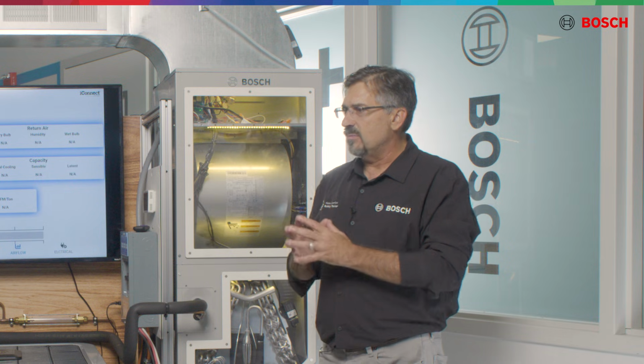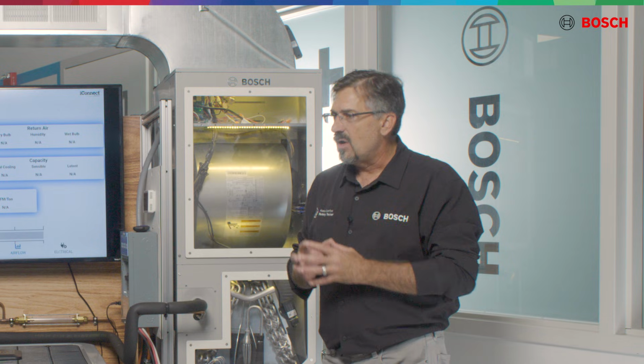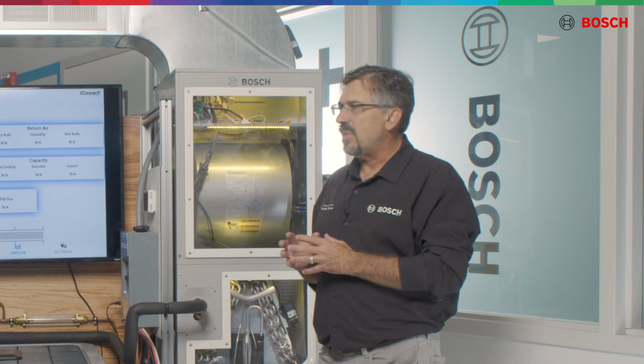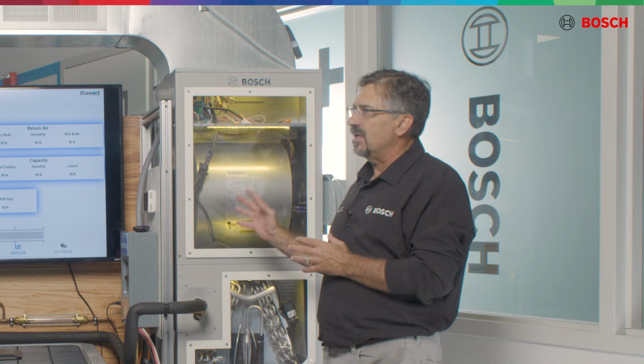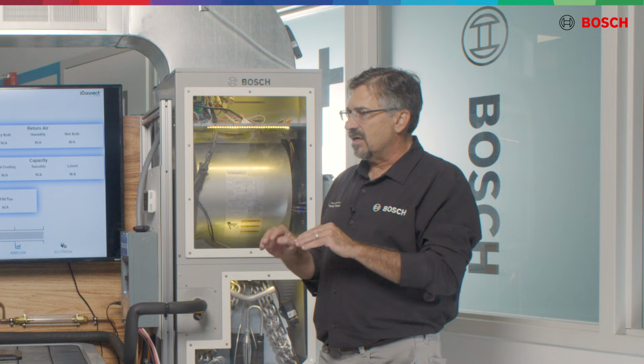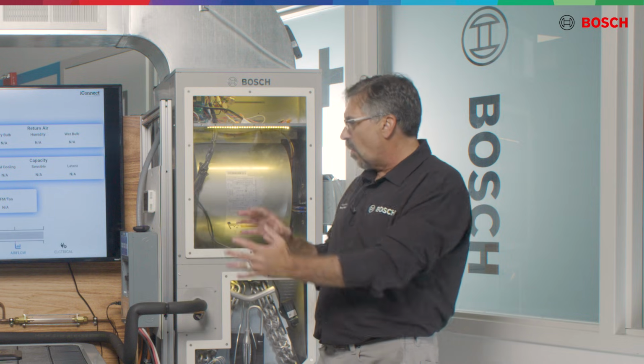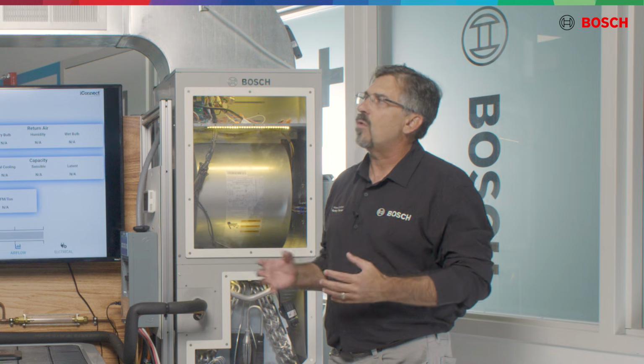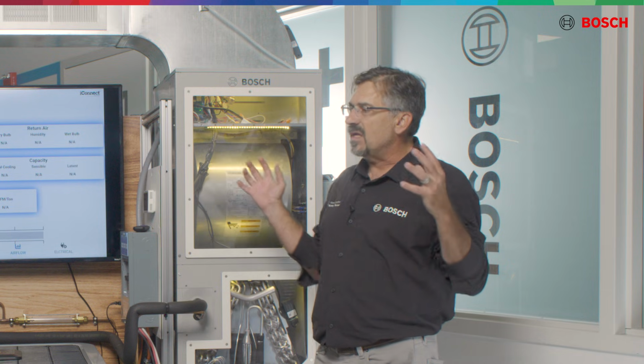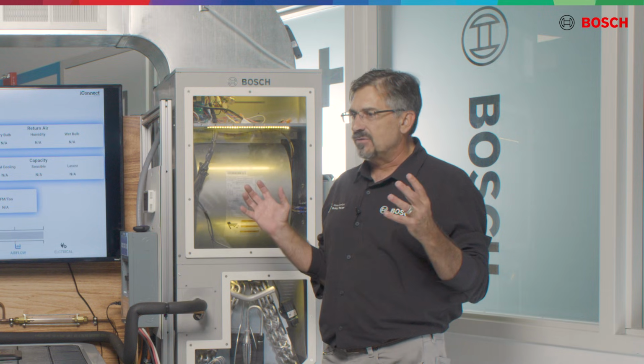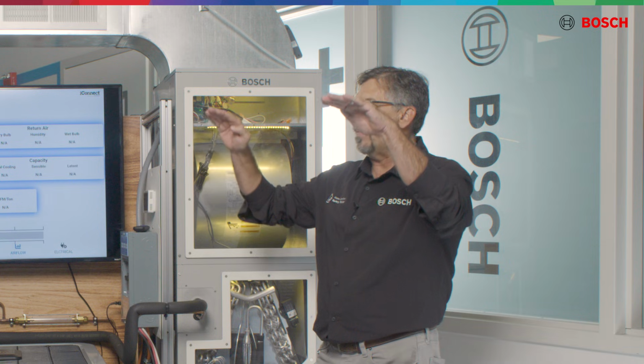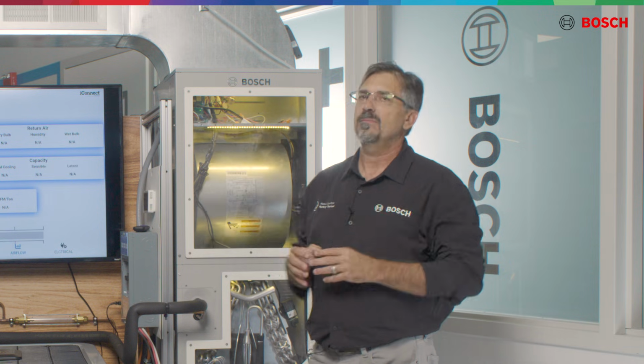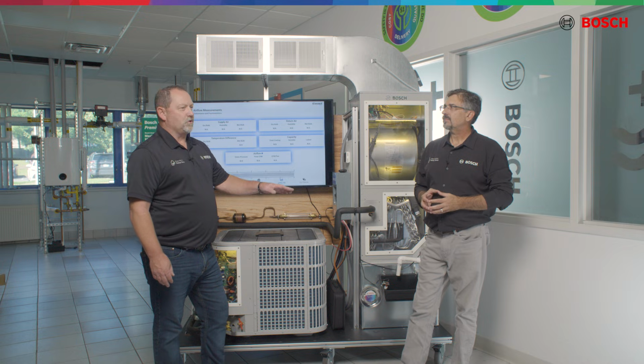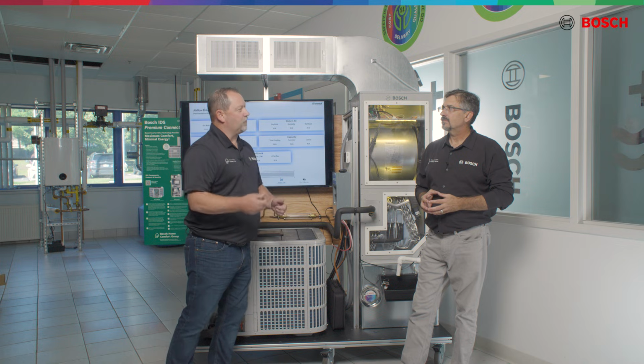So when we have hot, humid air entering our house, we need to vary the capacity of the outdoor unit to match the indoor load. So we're going to take our system and ramp it up to feed more refrigerant to this system to make our coil colder to overcome the infiltration. As the infiltration is overcome, the system's going to back down and get to its happy spot. So you mentioned changing coil temperature. So what actually causes a coil temperature to go up and down?